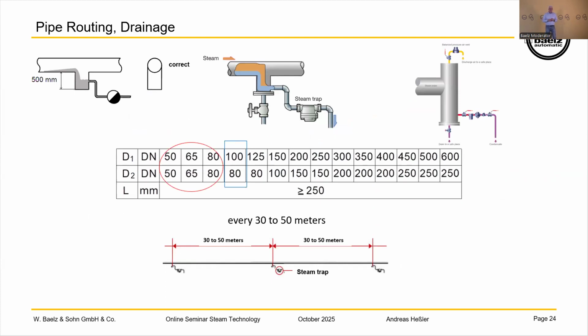On this slide, I want to show you that when you are draining a steam pipe, an extension must always be provided. So be sure that when you have, for example, a DN50 pipe, as I circled in red, your drain extension at the bottom is minimum 500 millimeters and DN50, and then drain from there. If you have a bigger one than DN80, you can make the extension smaller as shown in this table.